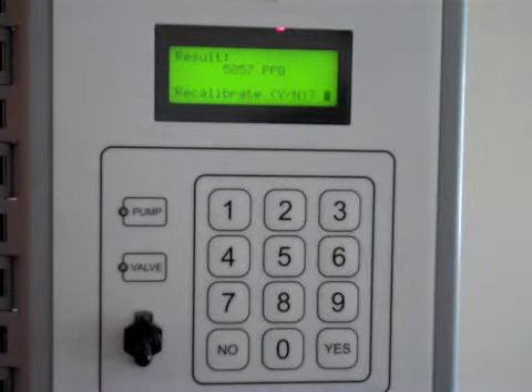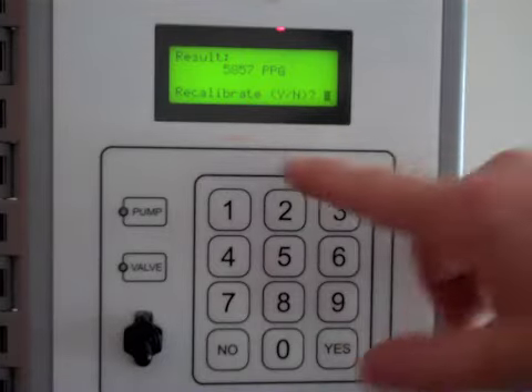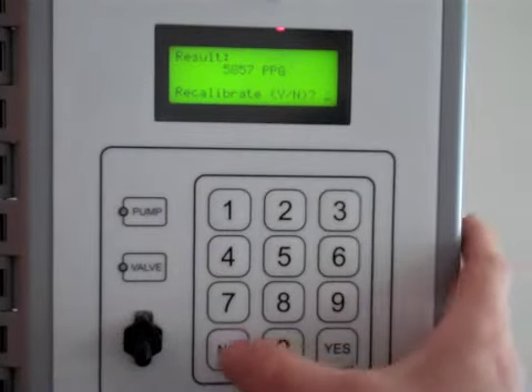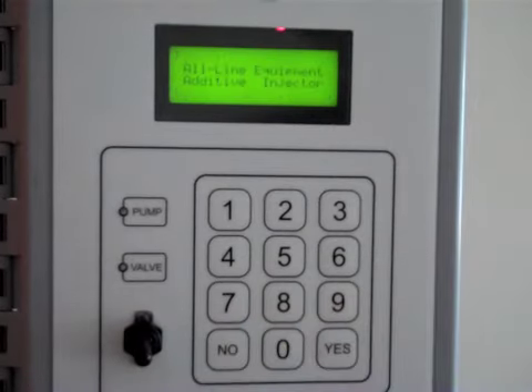So it's adjusted the pulses per gallon of the additive meter to a new number. It then prompts me if I'd like to recalibrate, and it'll do the process again - that's just a verification process. It's exactly the same: you pump, it says how much it pumped, you enter what it actually was, and it adjusts the number. At this point I'm not going to do a recalibration. And that's it, you're out of the setup.